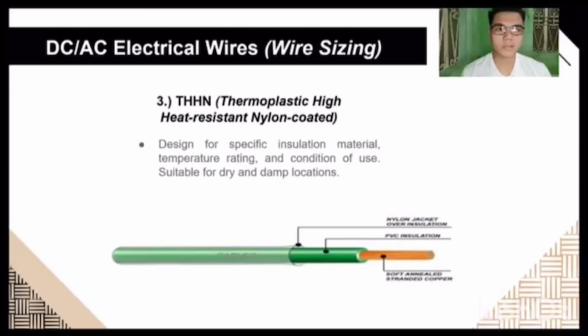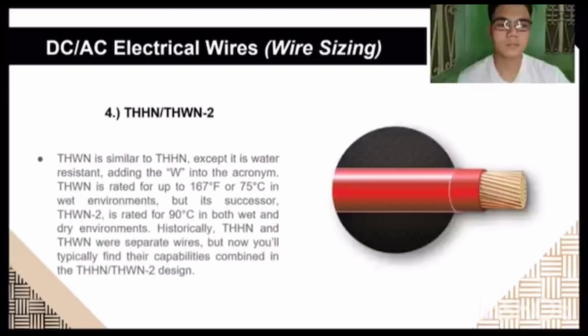THHN, or thermoplastic high heat resistant nylon coated, designed for a specific insulation material, temperature rating, and condition of use. Suitable for dry and damp locations. It's designed with a specific insulation material, temperature rating, and condition of use for electrical wire and cable. Number 4. THWN or THWN-2 is similar to THHN, or thermoplastic high heat resistant nylon coated wire, except it is water resistant, adding the W into the acronym. THWN is rated for up to 167 Fahrenheit or 75 degrees Celsius in wet environments, but its successor, THWN-2, is rated for 90 degrees Celsius in both wet and dry environments.